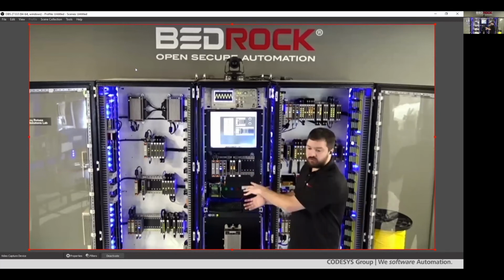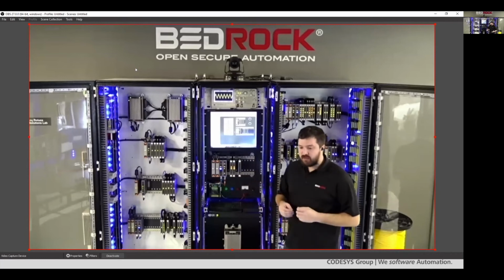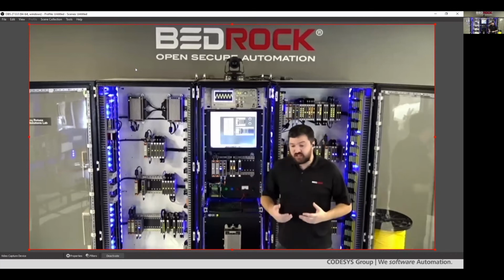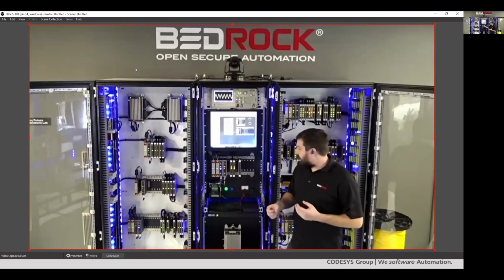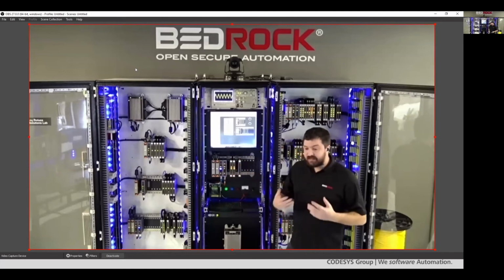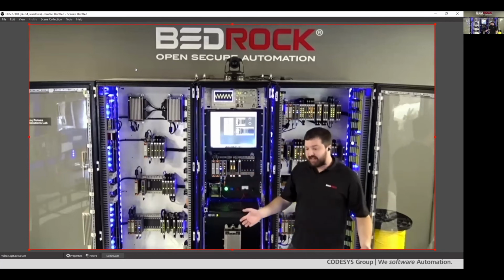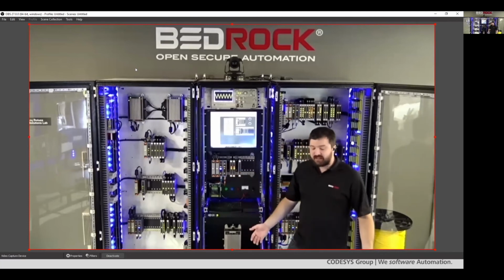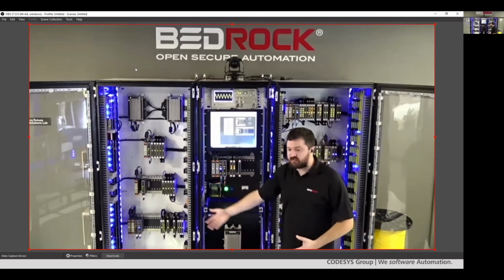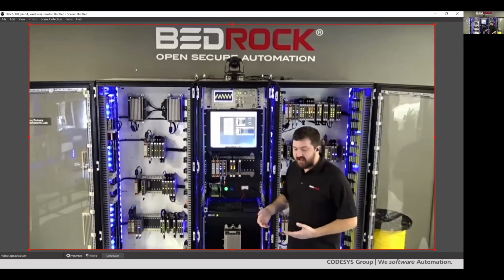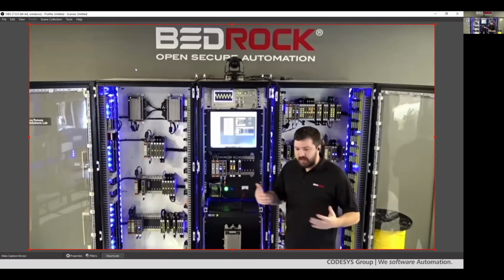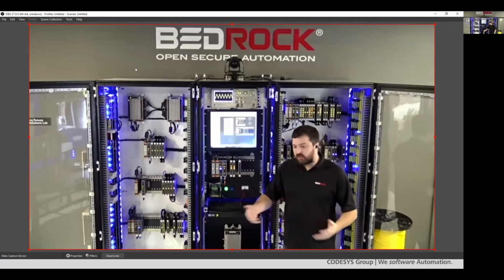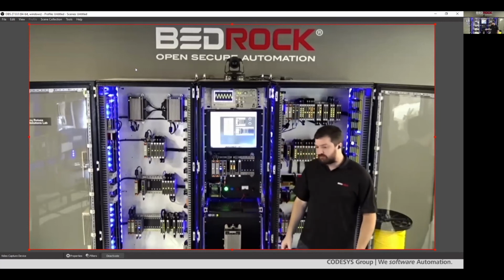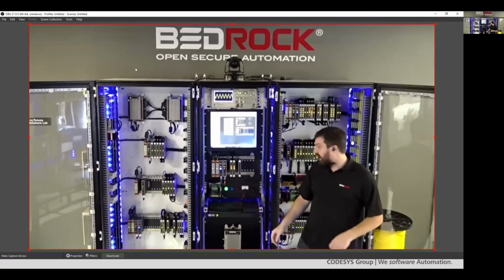A very important thing when it comes to securing your system is that you don't rely only on one centralized SCADA server connection. If that SCADA system gets compromised, you no longer have a connection to any of your controllers. If everything was on one centralized SCADA server and that connection broke, you wouldn't be able to connect to any of it, and that sets you up really well for ransomware type attacks.